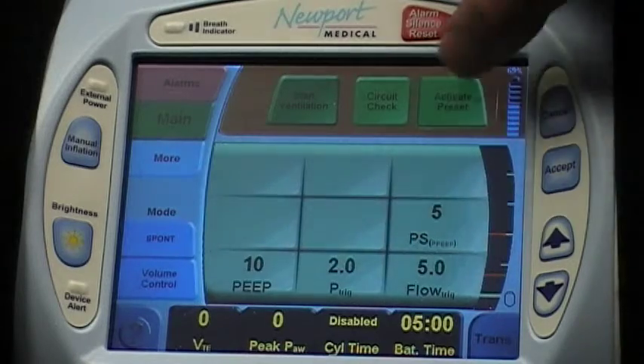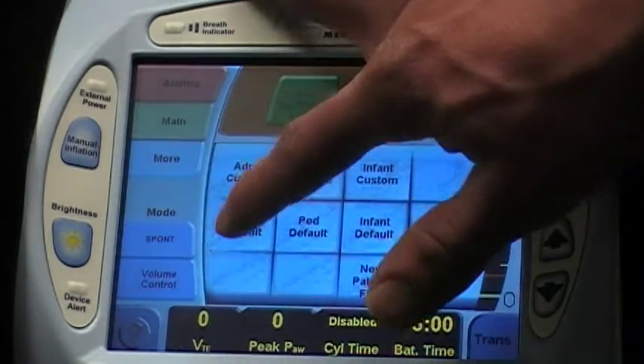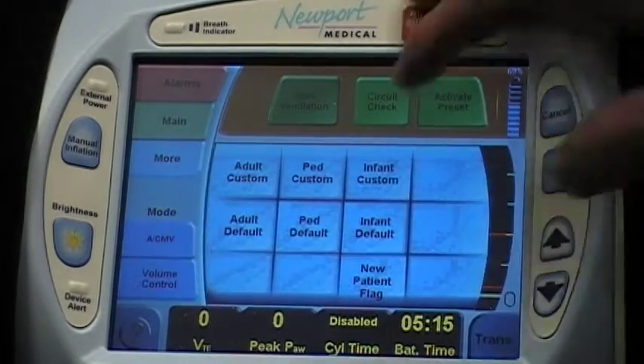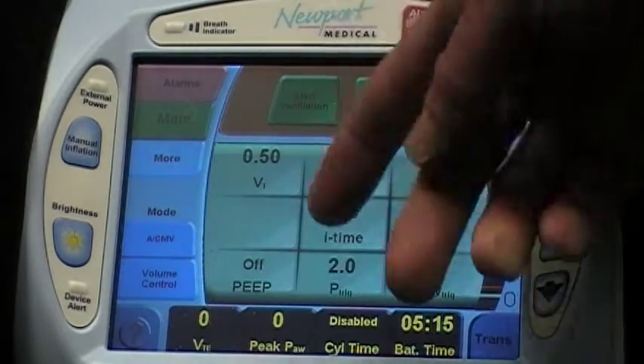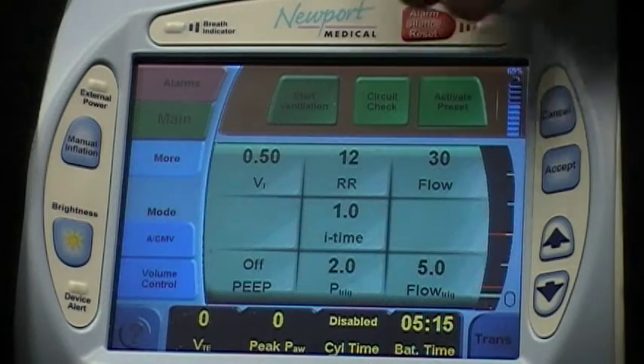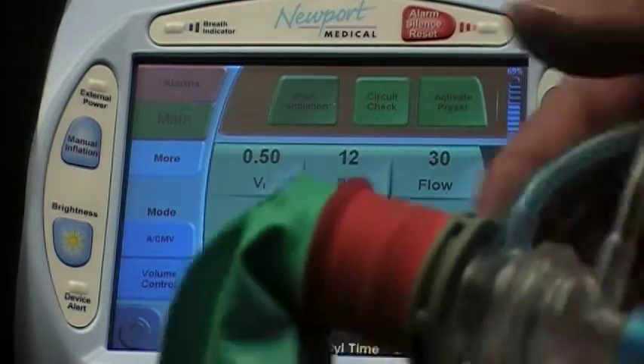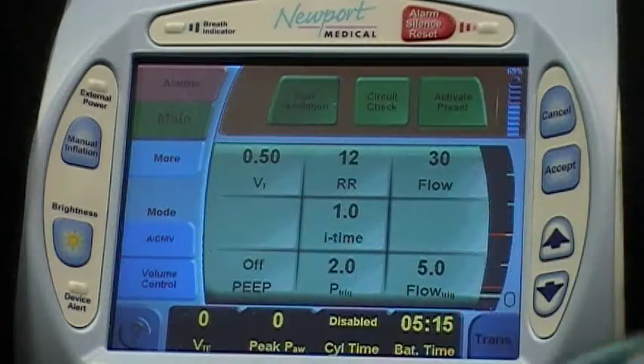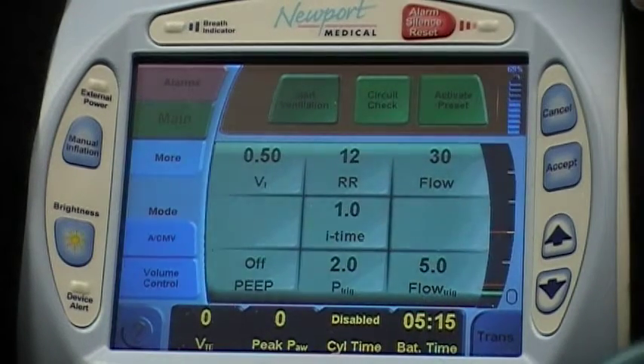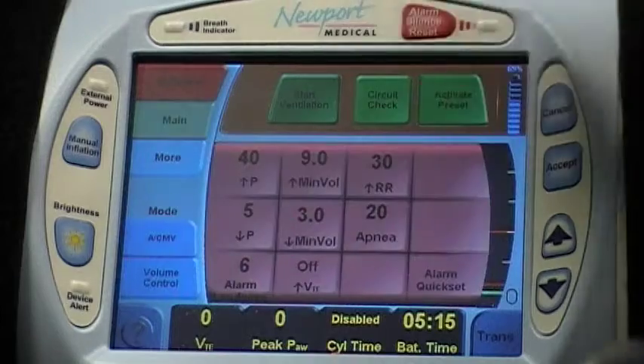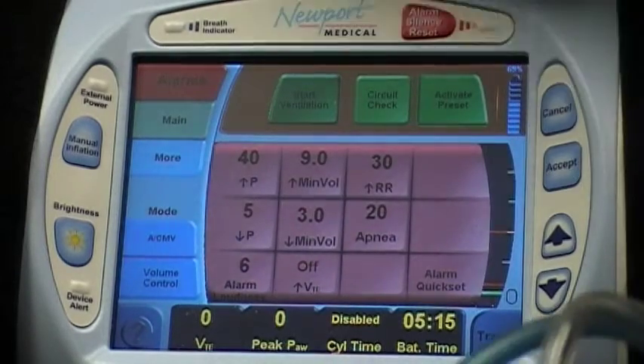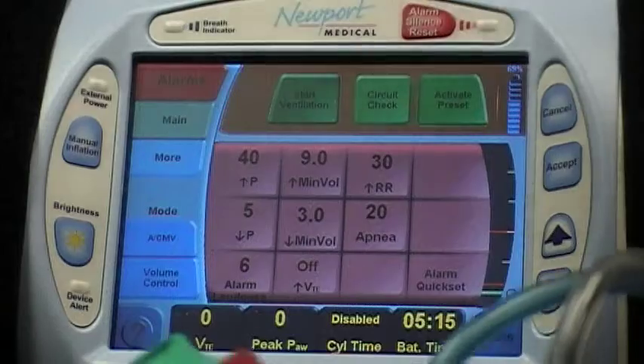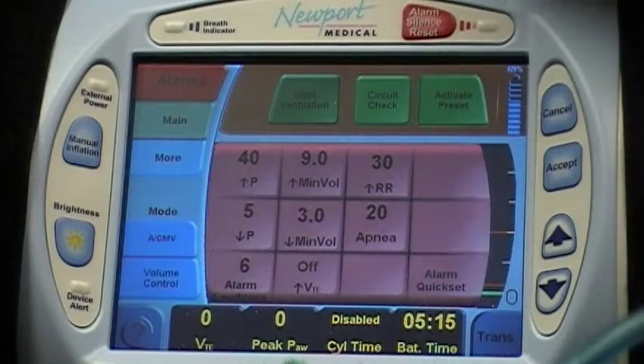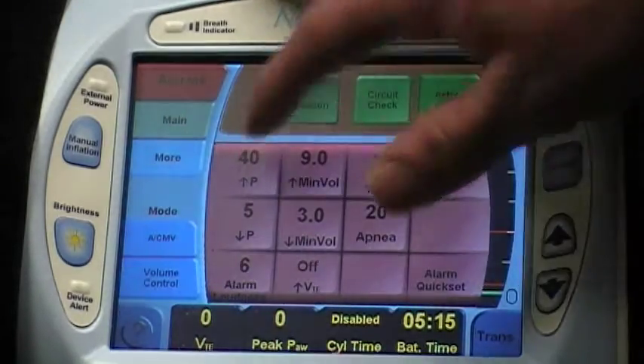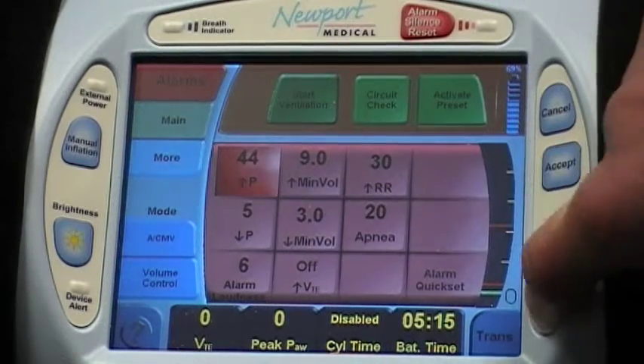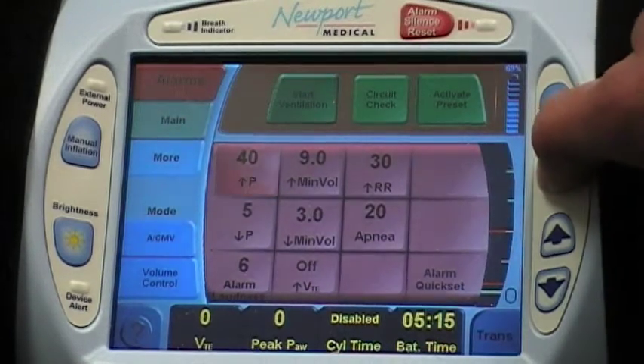For this class, I'm just going to go to activate, preset, adult default. So again, my PEEP's turned off, 500 tidal volume, respiratory rate 12. We're going to go ahead from here. We can talk about the alarms. To change any alarms, if you're on a call and you have some alarms going off, but you feel like you're within the correct parameters, you can come in here and change your alarms and increase them to keep them from going off.